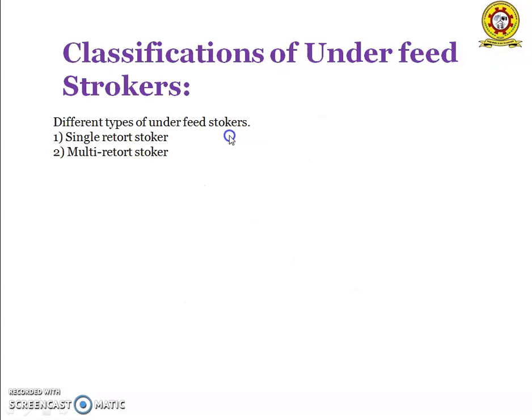The classifications of under feed stokers: under feed stokers are broadly classified into two types — single retort stoker and multi-retort stoker. The single retort stoker consists of a trough-shaped retort to which the fuel is fed by a reciprocating ram or screw conveyor. The capacity of this stoker ranges from 100 to 2000 kg of coal burned per hour. The second one is the multi-retort stoker. The coal falling from the hopper is pushed forward during the inward stroke of the stoker.